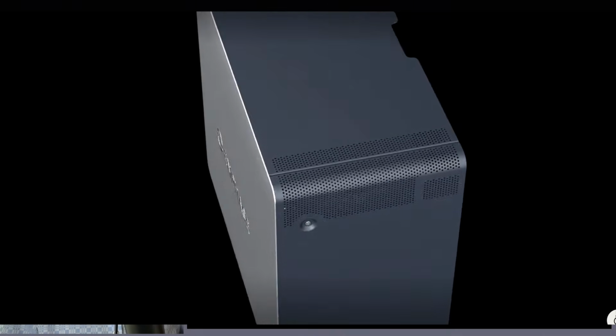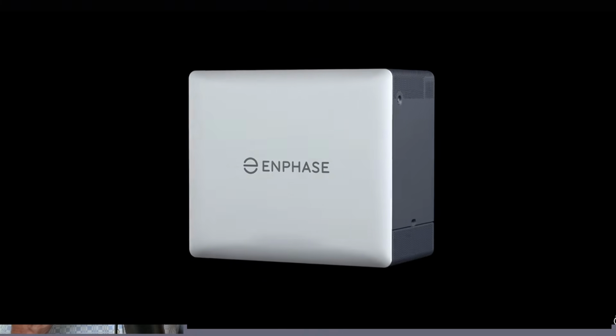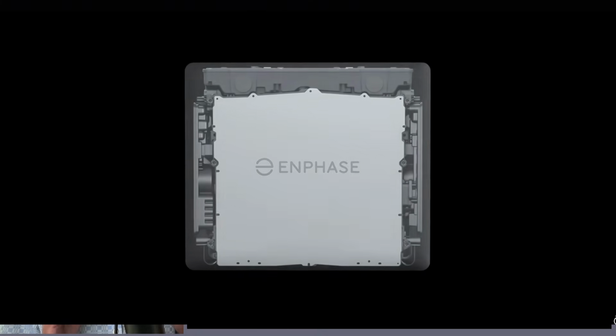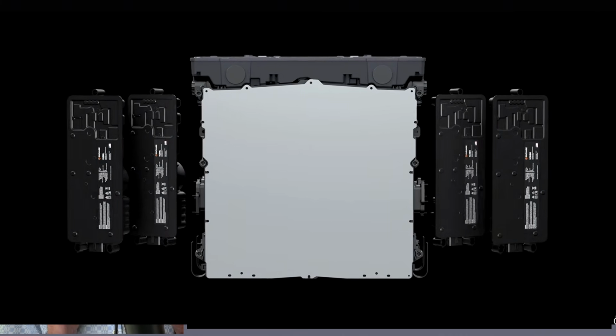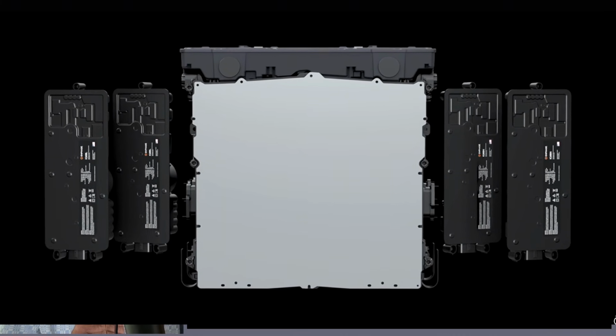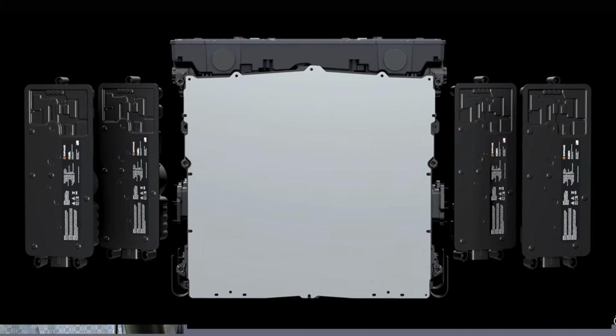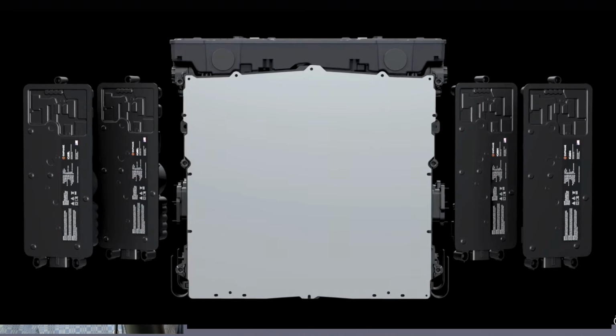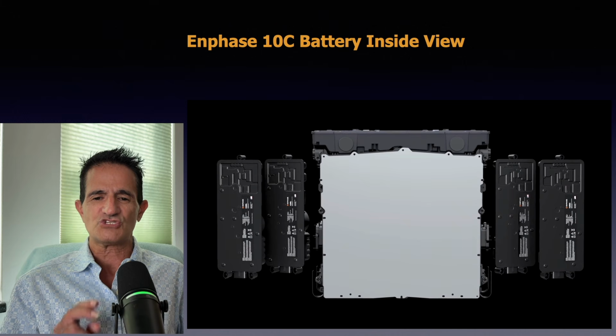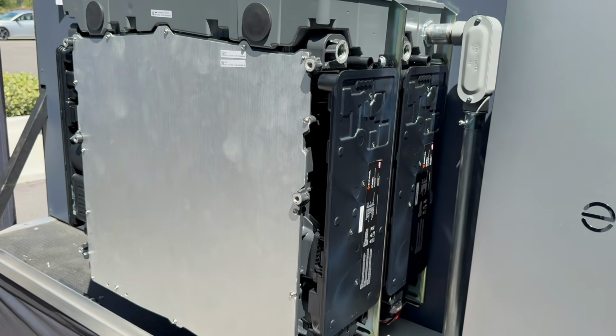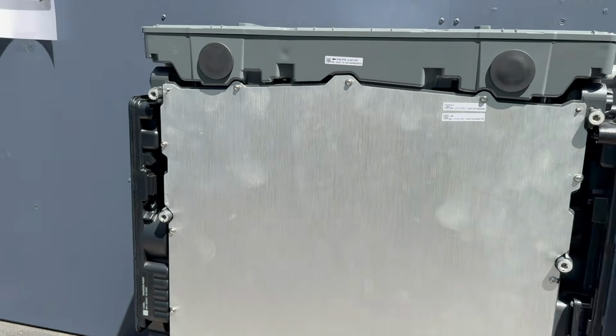Now let's look at the 10C battery inside view. Microinverters, but these are on the side, and this allows them to have more of a cube shape rather than a rectangle shape. Also, the microinverters inside the 10C, 2 of them are 120 volt, and that allows neutral forming. The 10C has two 5 kW batteries stacked.